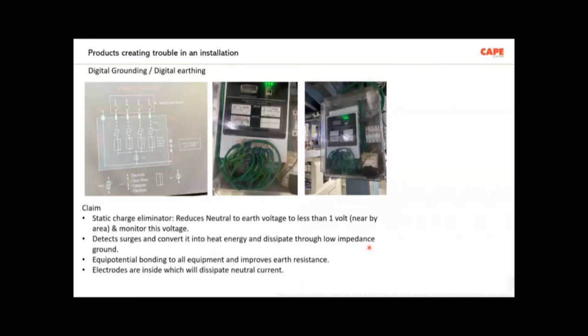The other product which is used, which is actually inviting fire or accident, is called a digital grounding device. This is a new trend in the industry to use this particular device. The manufacturers claim it as a solution for all your problems. They say you don't need earthing, this will absorb fault current, this will absorb neutral current, this will reduce neutral to earth voltage, and all the problems faced by the electrical engineer on a daily basis have been solved by this particular product. This is what the manufacturer claims.